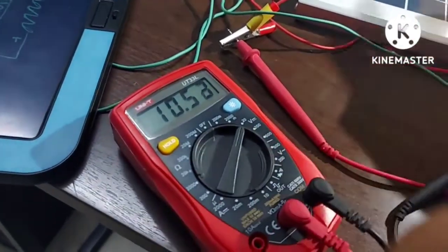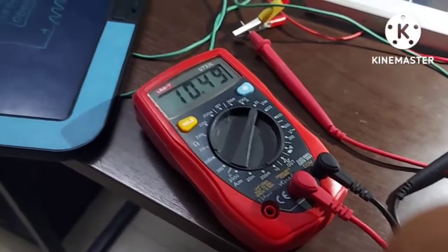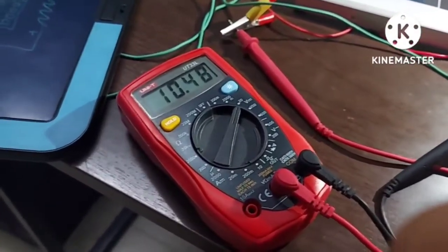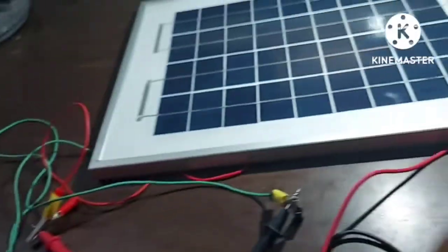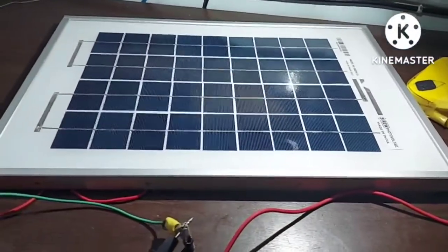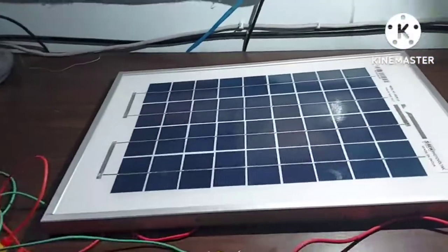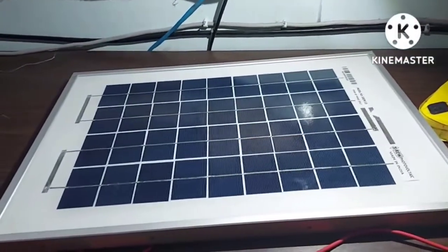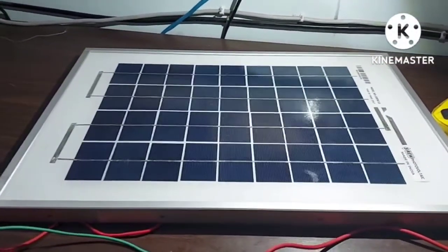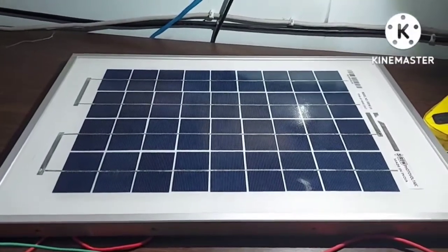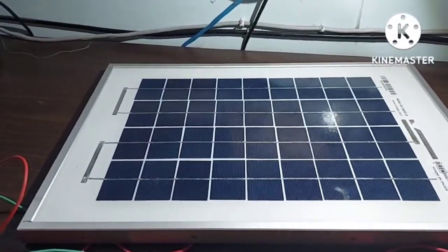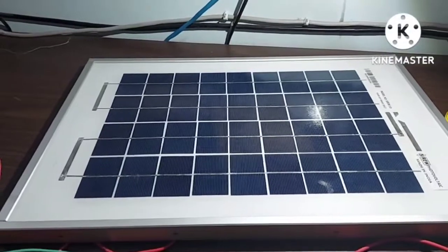Solar panels will generate only DC, because the cells work on a similar principle as a battery in which there is a potential difference of electrons, which is why you will always find solar panels that only generate DC. Now there are some solar panels in the market which are labeled as AC solar panels, alternating current solar panels, and what they do is they incorporate a small micro inverter behind the panel to give AC. This is useful in some on-grid applications where we require AC, and it's much better than connecting a normal inverter to the panel, to prevent losses. That will be the topic for another video, so I'll cover it some other time.